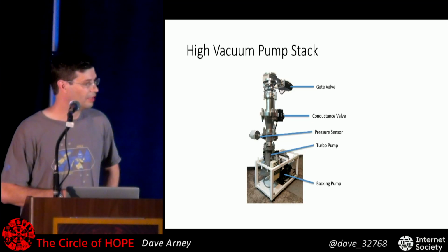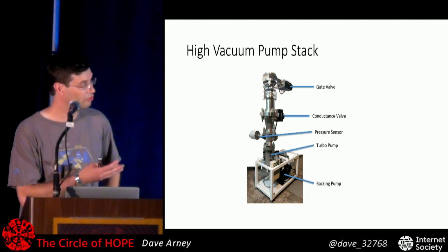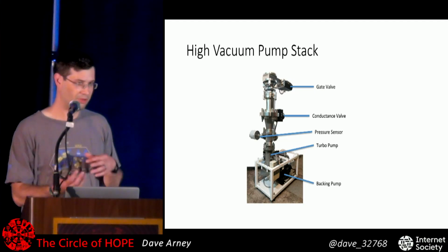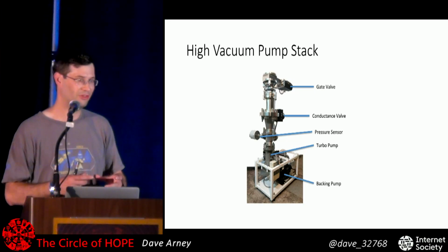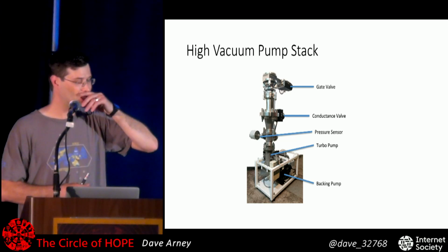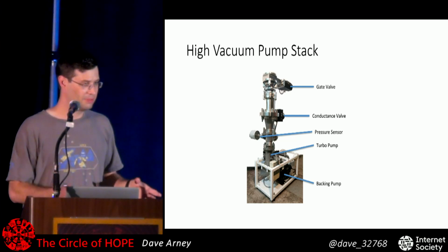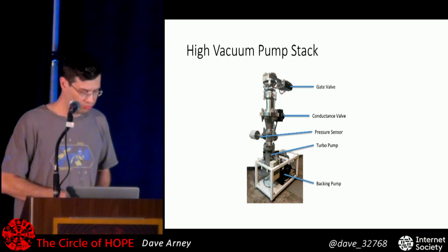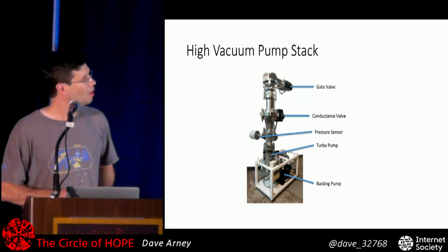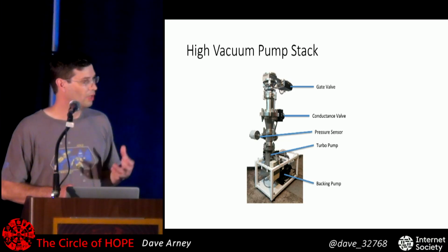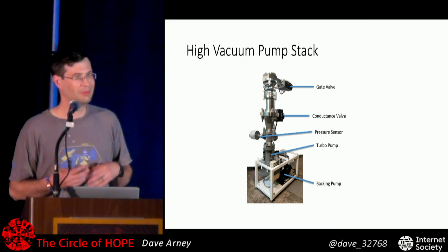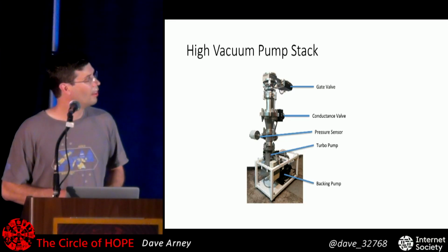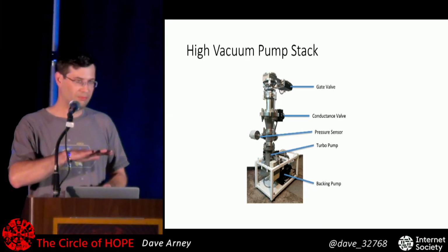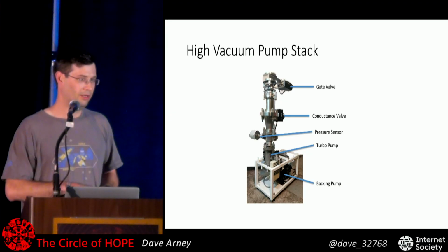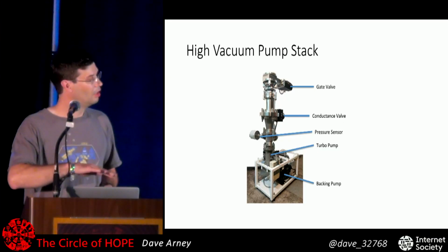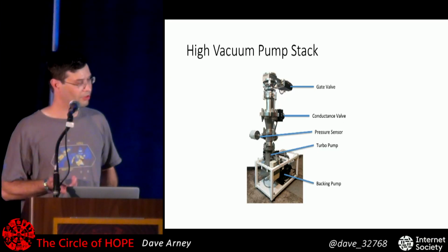So it gets you really a pretty good vacuum. It's down far enough that you have to start worrying about, the main source of pressure inside this thing is water vapor that's gotten bound up in the stainless steel surface of the interior of all your parts. And that sort of slowly creeps back out. And that's most of what's inside this when it's running. There's a conductance valve here because we don't actually want the chamber to be at that low of a vacuum. We want maybe 10 to the minus 3rd torr, a few millitorr. So there's a conductance valve here, which is just in this case, it's just a big flapper. And when it's horizontal, it stops molecules from bouncing out. When it's vertical, they pass through more easily, and so the pressure in the chamber drops.